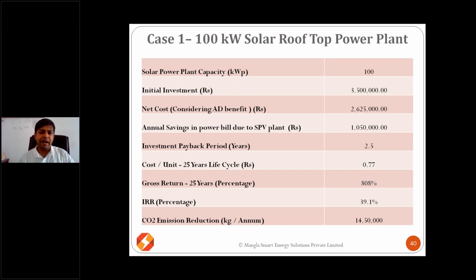With this power plant, they will be able to generate nearly 1,50,000 units of energy per annum. Since this was installed under a net feed-in mechanism, we needed to consider their maximum consumption. Their base load consumption was around 90 kilowatts, but we went for a 100 kilowatt plant under the net feed-in mechanism.